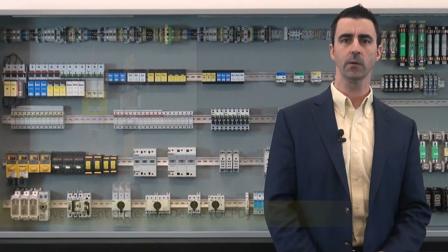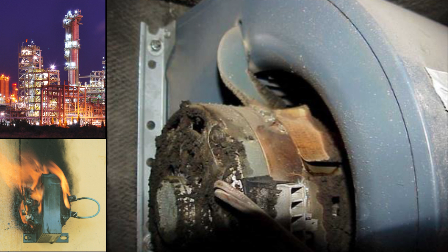Electrical distribution systems can be simple or complicated. However, they cannot be absolutely fail-safe and are subject to destructive overcurrent events such as overloads, ground faults, or short circuits. Harsh environments, general deterioration, damage, excessive electrical system expansion, or overloading are common factors leading to overcurrent events. Reliable overcurrent protective devices prevent or minimize costly damage to transformers, conductors, motors, and many other components that make up a complete power distribution system.